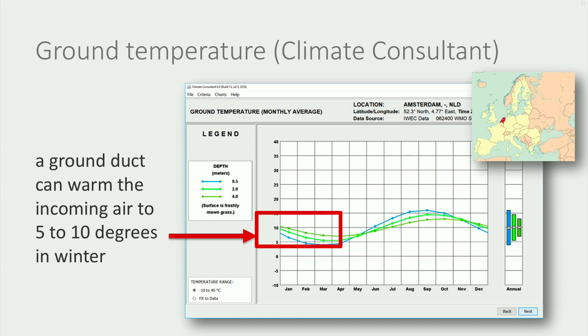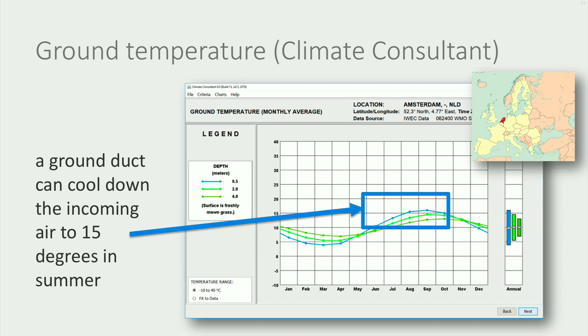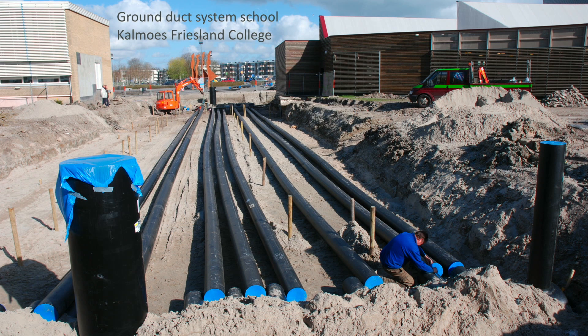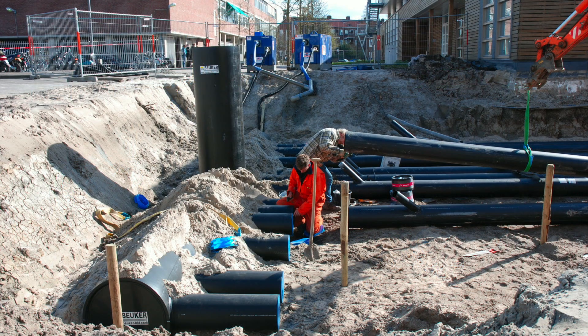A ground duct is able to warm up the incoming outdoor air to around 5 to 10 degrees in winter. And in summer, the incoming air can be cooled down to around 15 degrees, even when the outdoor temperature is 25 degrees. Here you can see an example of a project for a school, where several parallel ground ducts with a total length of more than 100 meters are buried at a depth of 2 meters.